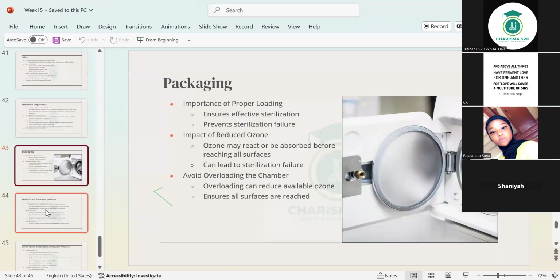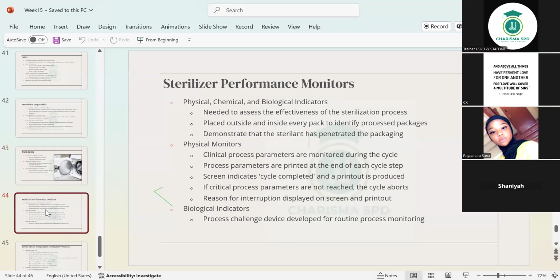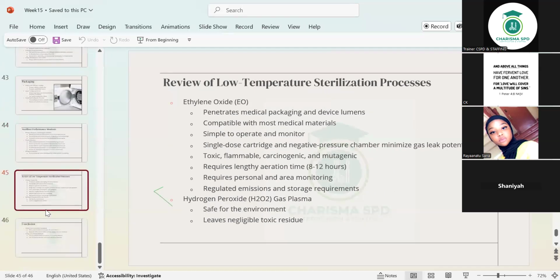All right, the packaging, the same thing. Proper loading, don't overload. That's the same thing that's being repeated. So your loading should be something that you always make sure you're doing right. The performance monitors are always going to be there. The physical, chemical, and biological indicators, they're always going to be there for you to use. Then the review of low temperature sterilization processes. The ethylene oxide penetrates medical packaging and device lumens. Compatible with most medical materials. Simple to operate and monitor.